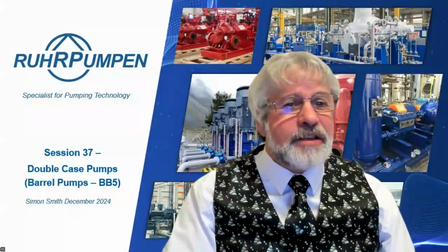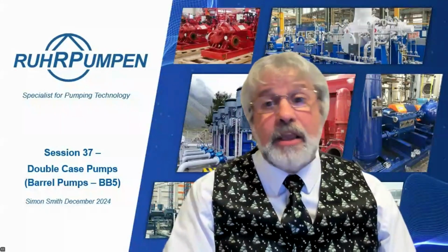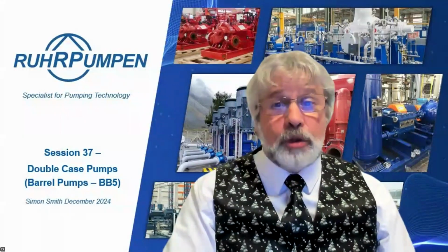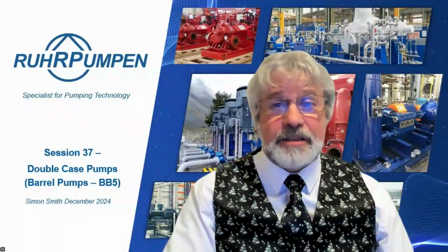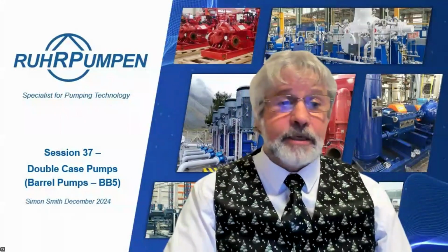The anonymous attendee again, which one is a costly design, a volute type or diffuser design? Generally, the diffuser design will be less expensive because it is lighter and has less material in the casing.